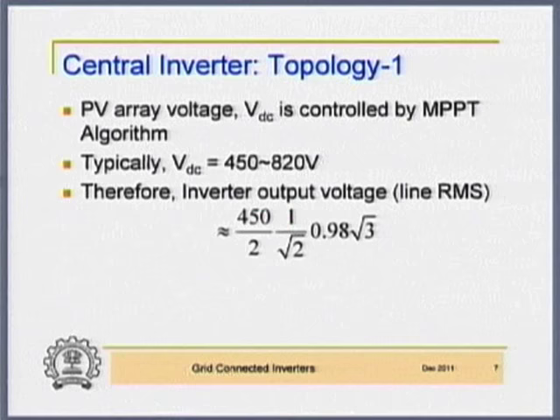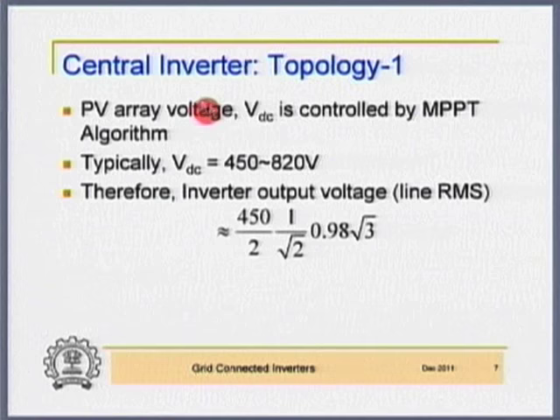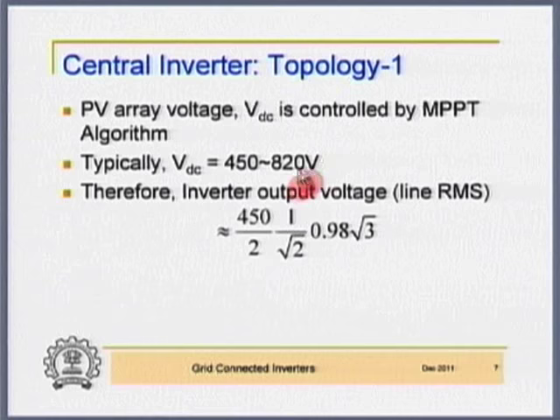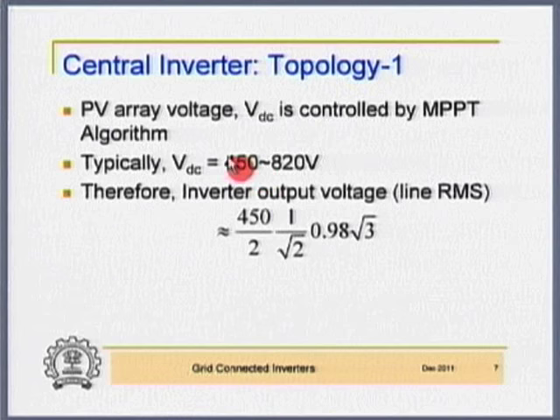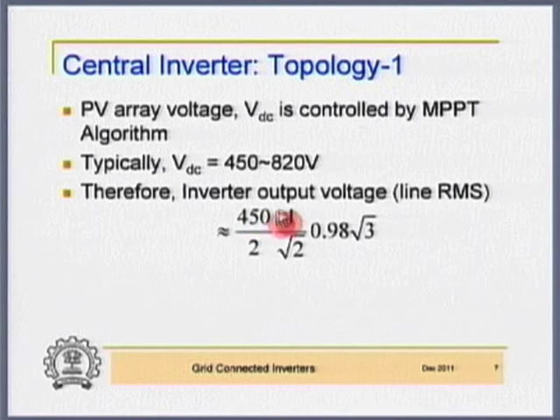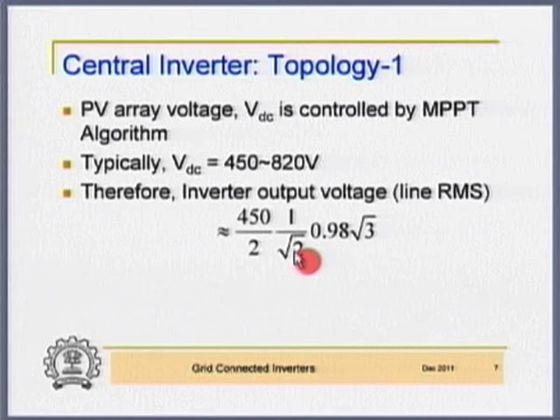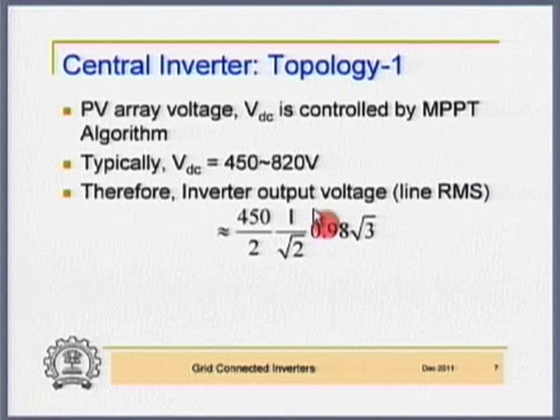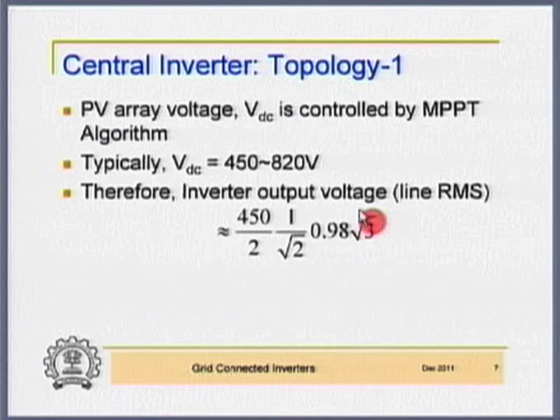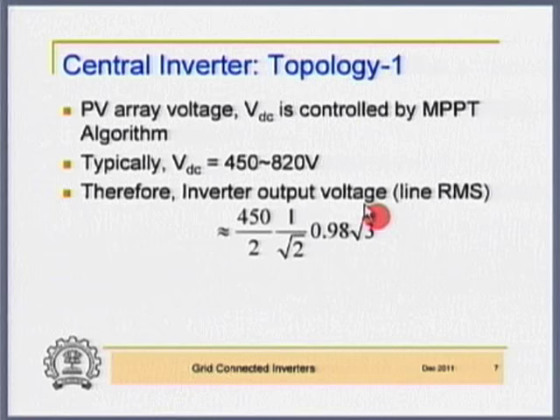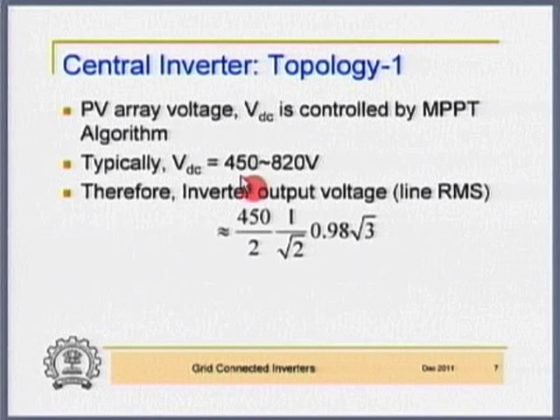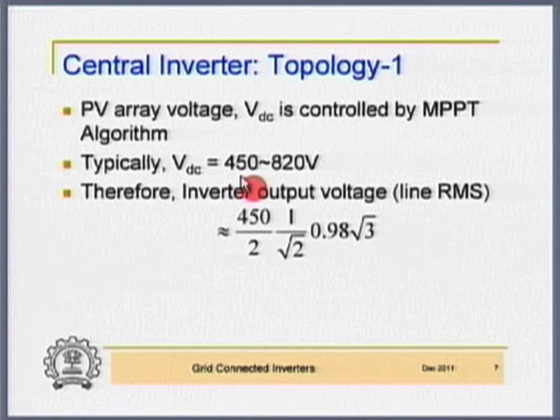The PV array voltage V_DC is directly controlled by the MPPT algorithm. The operating point of the string is determined by the MPPT. Typically, DC link voltage is of the order of 450 to 820 volts. When the DC link voltage is 450 V, the inverter output line RMS voltage would be: (450/2) × (1/√2), which gives the RMS phase voltage; multiplied by √3 gives the line voltage, with 0.98 as the modulation index. The V_DC reference is set by the MPPT and the remaining control stays the same.